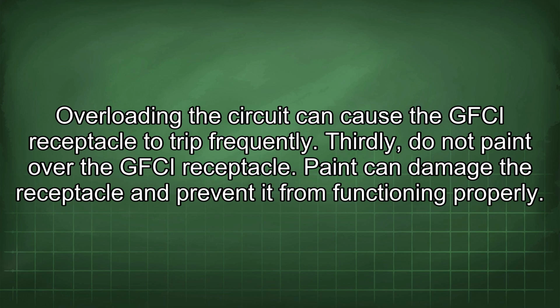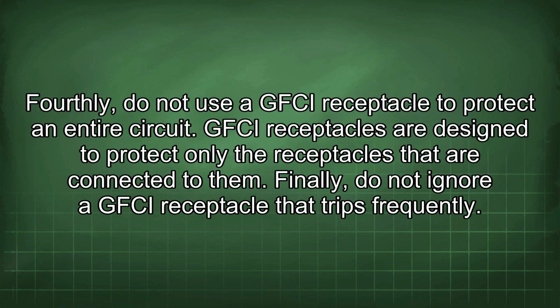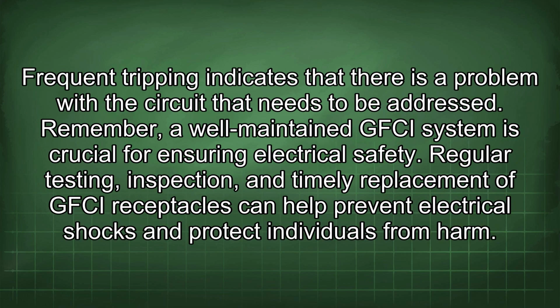Thirdly, do not paint over the GFCI receptacle. Paint can damage the receptacle and prevent it from functioning properly. Fourthly, do not use a GFCI receptacle to protect an entire circuit. GFCI receptacles are designed to protect only the receptacles that are connected to them. Finally, do not ignore a GFCI receptacle that trips frequently. Frequent tripping indicates that there is a problem with the circuit that needs to be addressed.